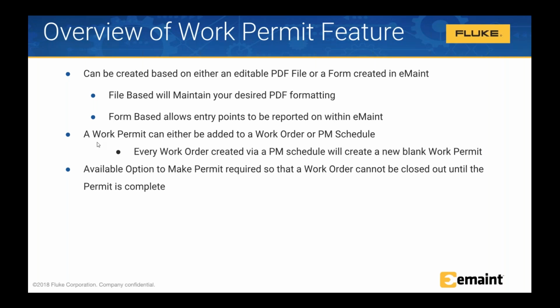Now, a work permit can be added either to a work order directly or to a PM schedule. When you add a work permit to a PM schedule, every single work order that's generated via that PM schedule will have the permit generated along with it as a blank document for somebody to complete for that work order.